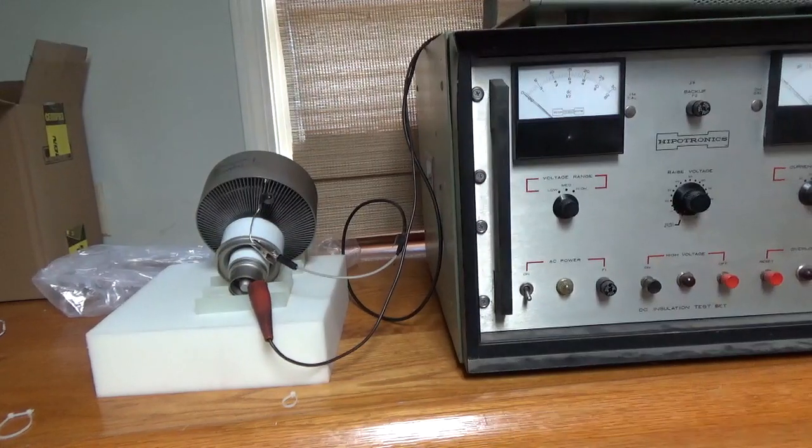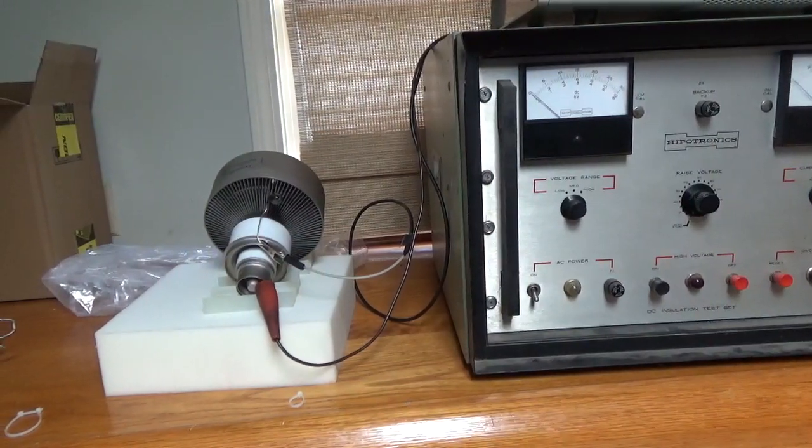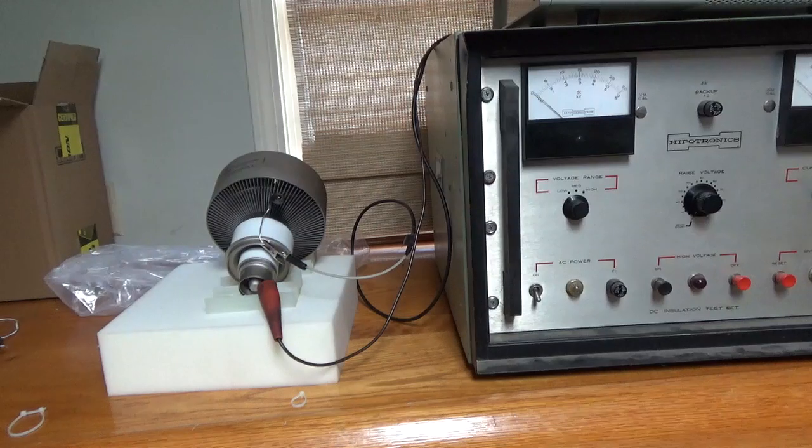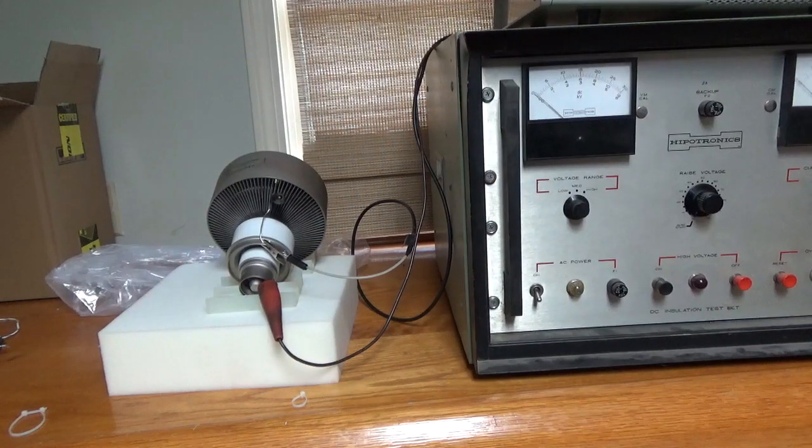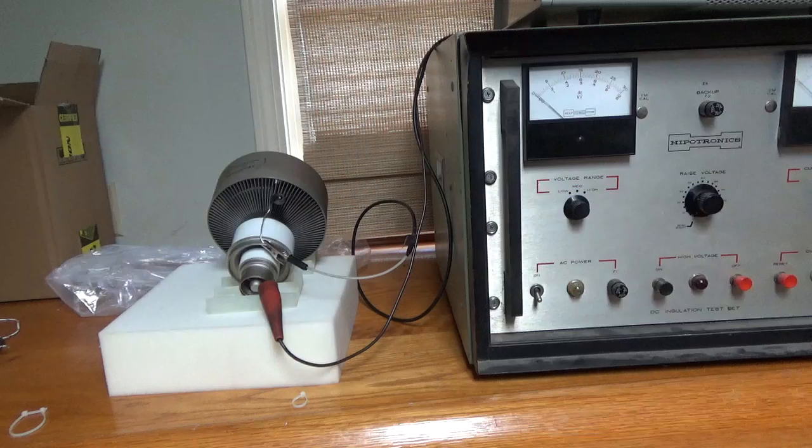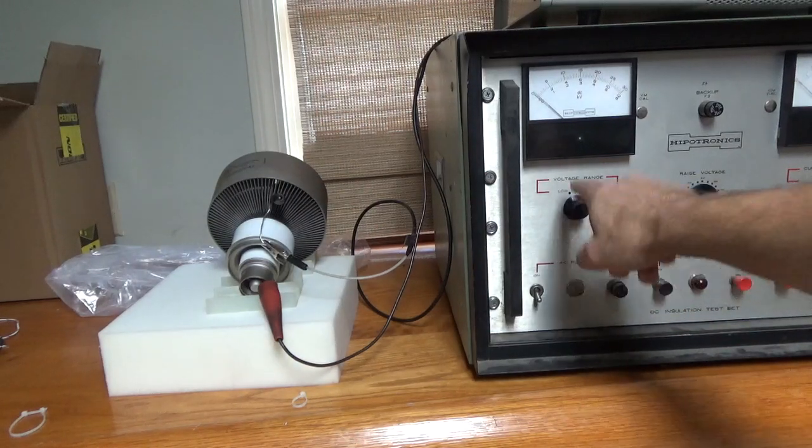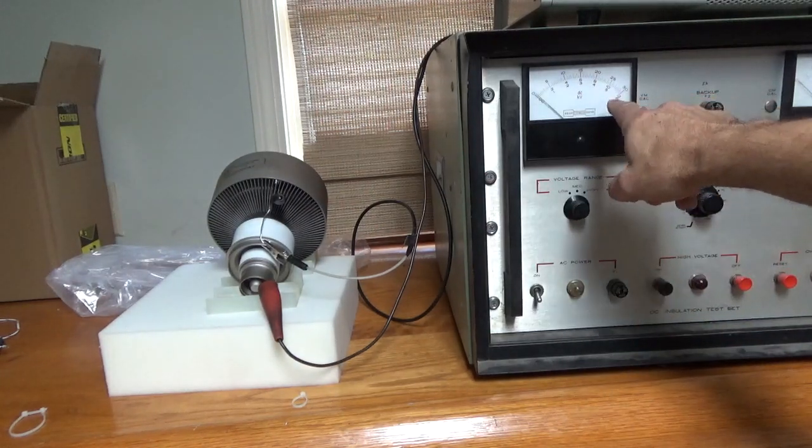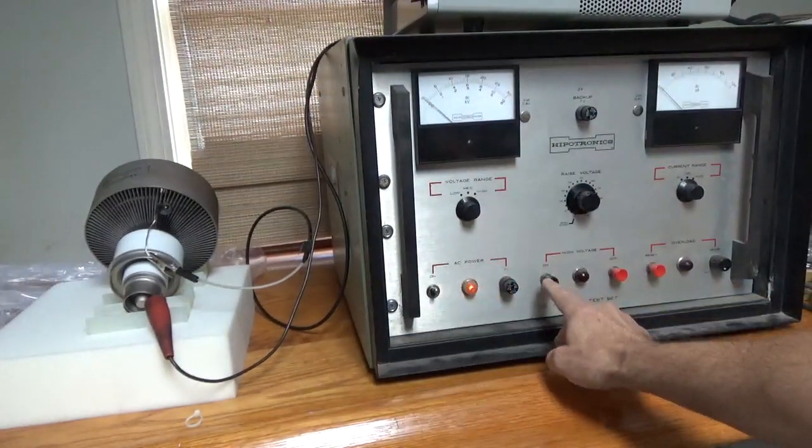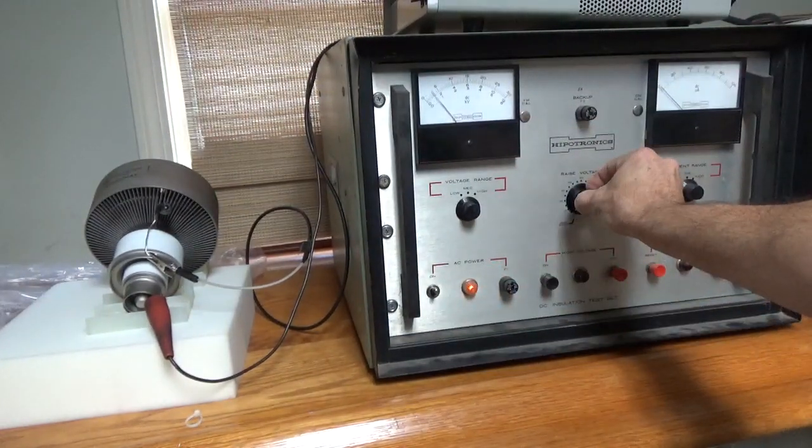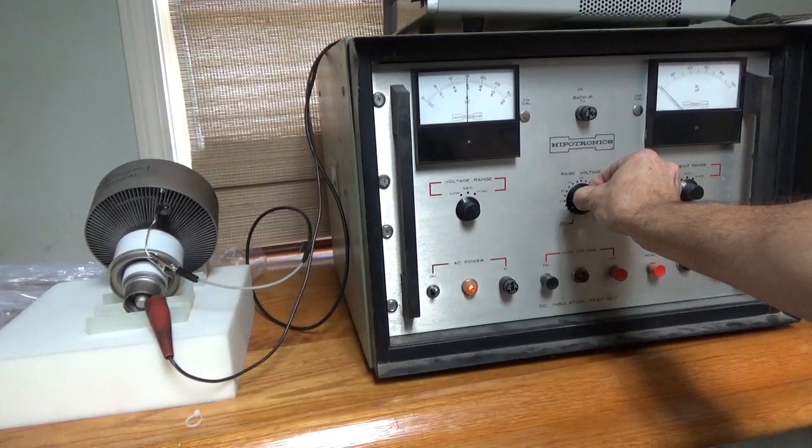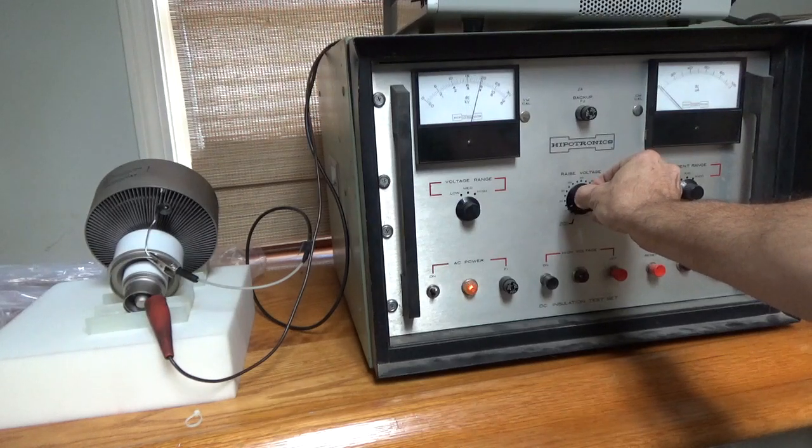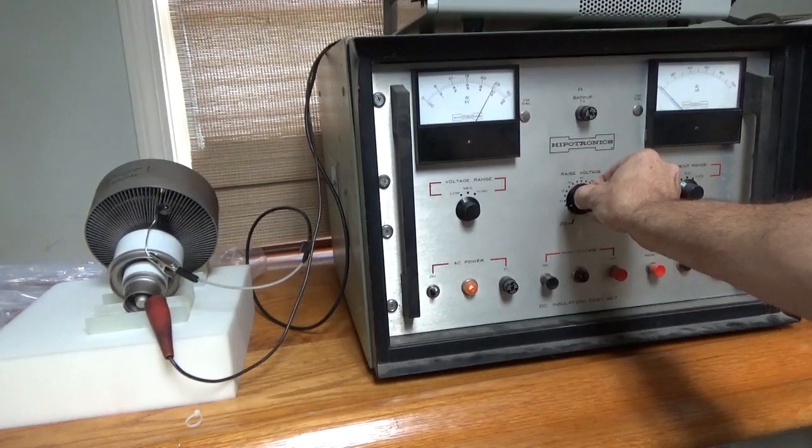Okay, time to high pot between the grid and the filament. So I'm going to bring it up to 5 kV DC and reverse the polarity. Grid is grounded to the anode. Meter is now set to the lowest setting, zero to 6 kV DC. Turn it on. Let's see what we get. We're good.